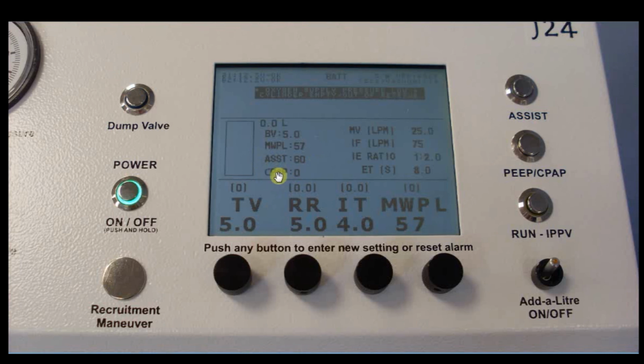Underneath that we have a CPAP value of 0, and the CPAP is set by this button here, which says PEEP or CPAP, depending on which mode we're in, whether we're ventilating or spontaneous breathing. Pressing this CPAP button means that the MWPL will change to say CPAP, and we can set it with this knob. At the moment it's set to 0.